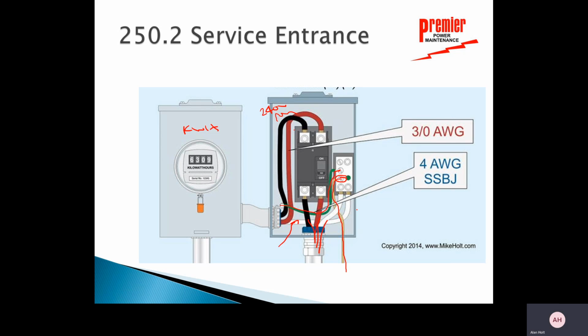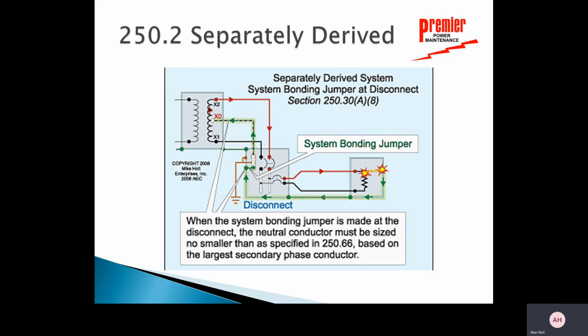Neutral and ground are tied together right there, but that is at the service entrance, okay? This number 4 AWG is the size of the cable, the supply side bonding jumper. So that is where it's connected together, where I connect ground to the neutral. And that's the only location in the world that I can have those two things tied together. So if I look at this separately derived system in detail, that's what I've got right here.